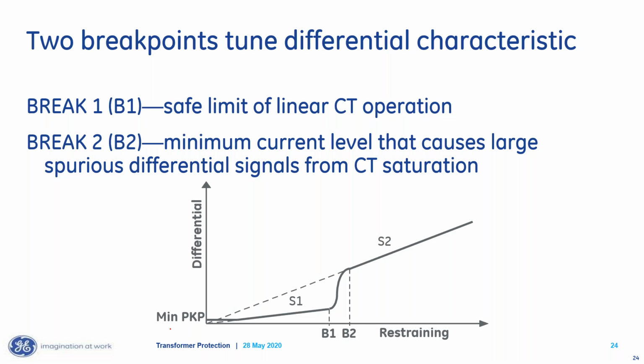Now, the upper break point should be the minimum current where you could get spurious differential because of CT saturation. What I've seen people do is calculate quantities for that. And if you're in a utility situation, you might have C800s and 3,000 or 4,000 or 5,000 CTs. And when you do that calculation, you have an upper break point of like 15. That's not a good upper break point. I like to be more conservative, set the thing so I am less likely to misoperate. I'll set that down around 4. Sometimes I'll set it just above the lower break point, but usually my recommendation is to set that around 4 per unit.